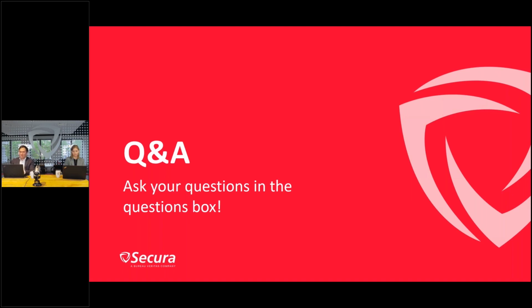Very good question, because most of the time in this webinar we have focused our attention on the medical device manufacturers and not so much on the medical device users, which are, of course, hospitals. The regulation itself doesn't apply to hospitals; it applies to the manufacturers. So the manufacturers of medical products or systems need to follow this regulation. They need to demonstrate compliance with those requirements in order to develop and sell the products on the European market. Now, the good news from the point of view of hospitals is that the mission is a bit simplified. If you are a hospital residing in one of the countries of the European Union, then basically every product available on the market that you can purchase in the EU should already have passed the MDR clearance, because that is the requirement for the product to be placed on the market in the first place. So from that point of view, the medical device regulation is a bit of a lower concern here.